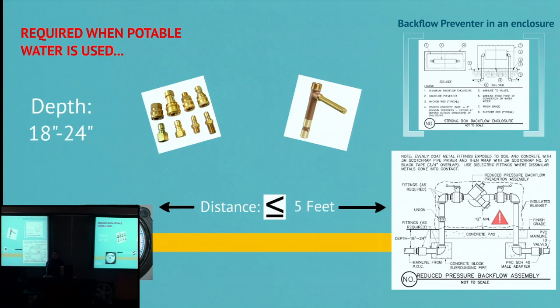But on the backflow preventer, there's a petcock, and you can get a gauge with a 1/4-inch fitting on it and screw it into the petcock that's on the upstream side of the backflow preventer. And then you need a screwdriver to turn on the petcock, and then the gauge will read what your static pressure is. And your static pressure is the pressure that you'll be starting your hydraulics from. And we won't go into hydraulics tonight because that really is a whole other discussion.